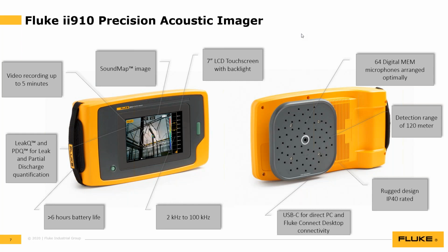All right, here's a more specific question. I know we're trying to keep things general, but maybe it's of use to other folks. We currently have capacitive sensors for partial discharge detection on our generators. To use the ii910, would the method have to have line of sound instead of line of sight access to the windings during a unit shutdown with the windings excited by a high voltage source?